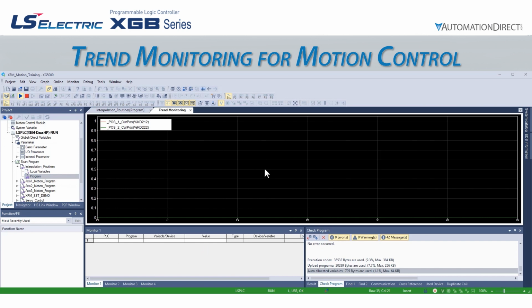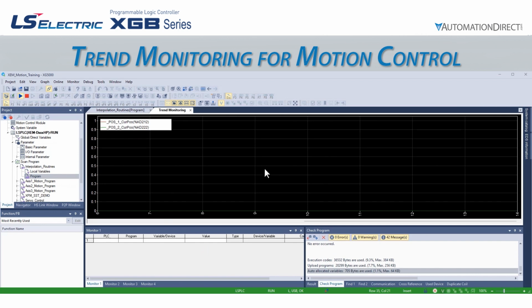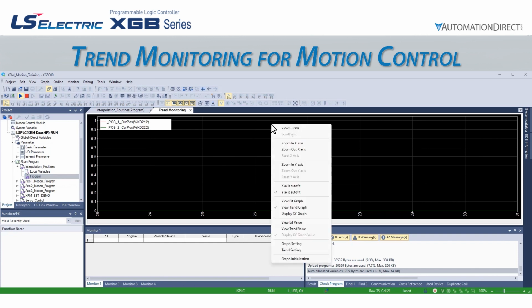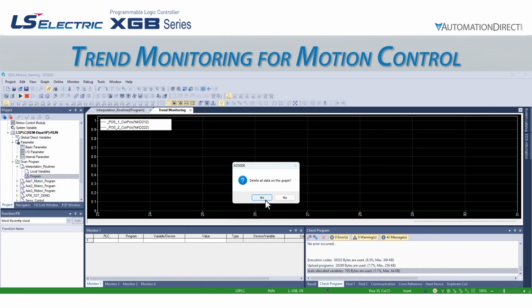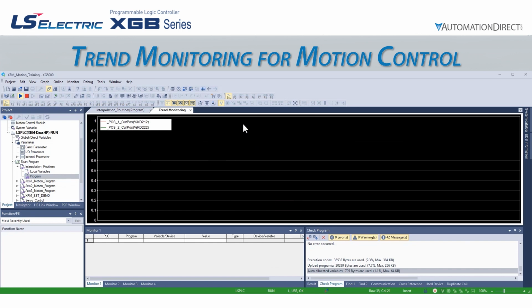As soon as we add these variables, we see trending go active because we have the trend monitor window loaded with valid data and are already in monitor mode. To stop trending, we need to go out of monitor mode. We will also need to reset the trend back to the default. To do this, we can right-click anywhere in the trend monitoring window and select Graph Initialization. We see that the view has now been reset.